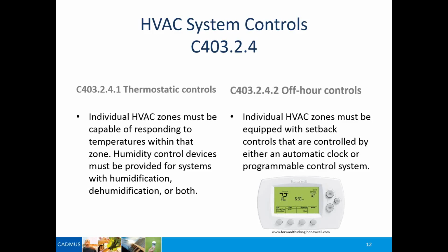So we're trying to maintain a temperature of say 75 degrees on the inside. It's the hottest day possible on the outside. The building's fully loaded with people. All the lights are turned on. We have all the equipment turned on, and that's worst case. But when you actually look at the way the system operates, it doesn't hit worst case. It doesn't have to deal with worst case loads a lot of the time. So we want our systems to be able to run as efficiently as possible at part loads. So when we especially start getting into large chillers, there will be a lot of control requirements to make sure that the capacity of the system actually matches what's going on in the building.